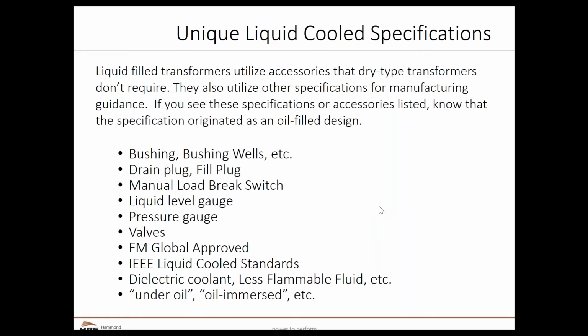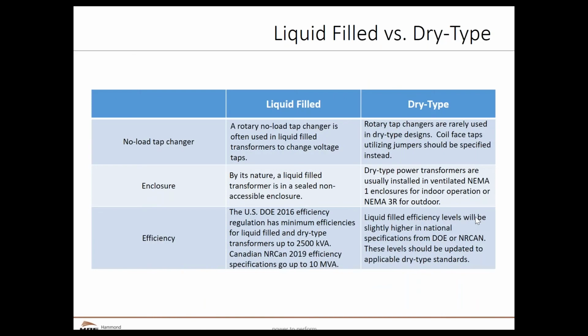And by the way, there is no dry type equivalent. So when somebody, again, hands us an oil spec, we can't meet this. Probably don't need them, but again, can't meet it. So there's a couple things. We sometimes run into a situation where a specification says no load tap changers. This is where you can install a relatively simple mechanical tap changer in the actual oil that the transformer itself is submerged in.